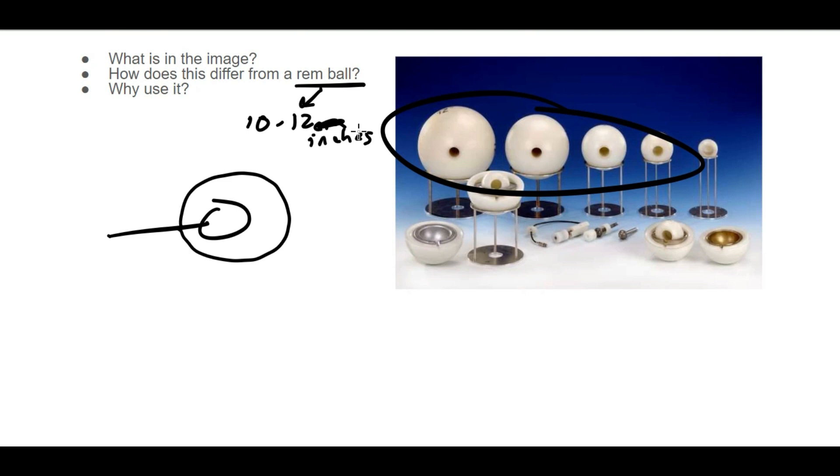They match the dose equivalent weighting factor for a neutron. Every REM ball is a Bonner sphere, but not every Bonner sphere is a REM ball. Often in the clinic, it's really nice to use a REM ball because you're going to get that dose equivalent.